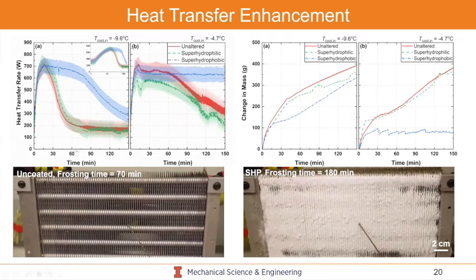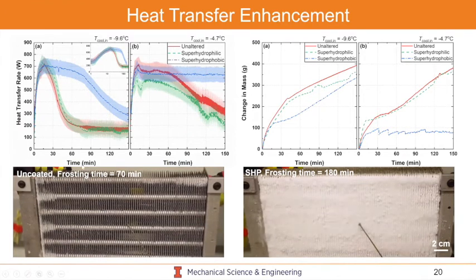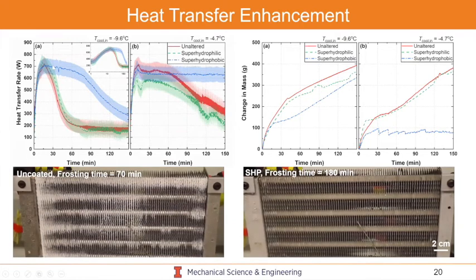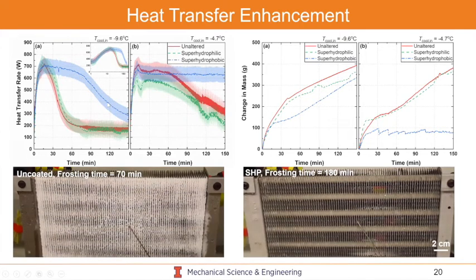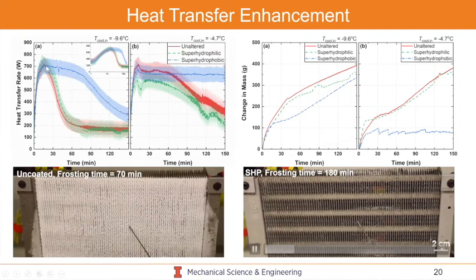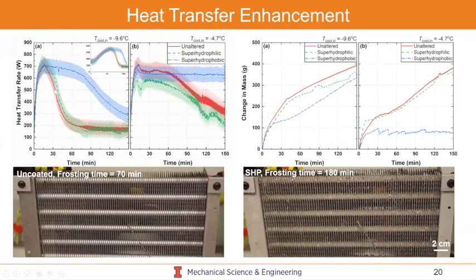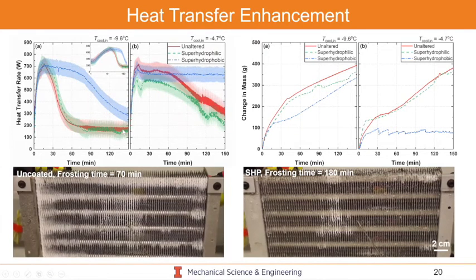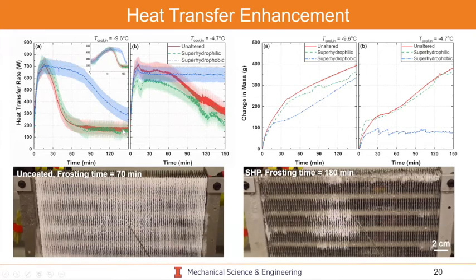What this equates to is, if you plot the heat transfer rate as a function of time, you maintain a very high heat transfer rate for the super hydrophobic heat exchanger, but your heat transfer rate on a wetting, as-is heat exchanger just decays because the frost grows on the surface, giving you very inefficient thermal pathways from your coolant to your air.